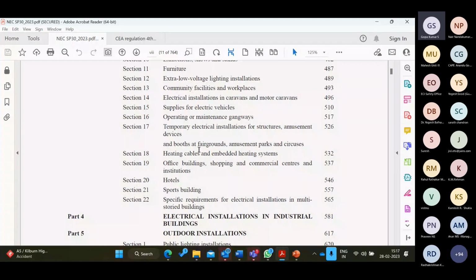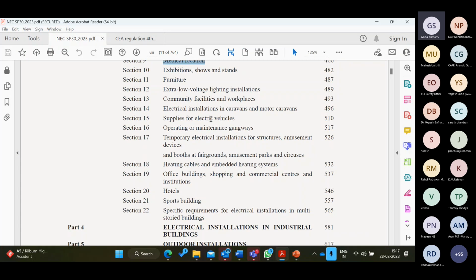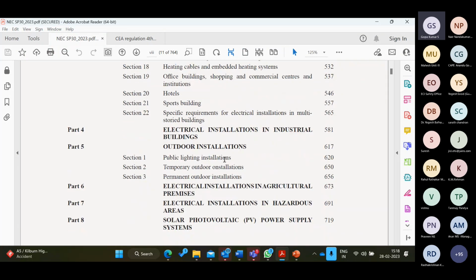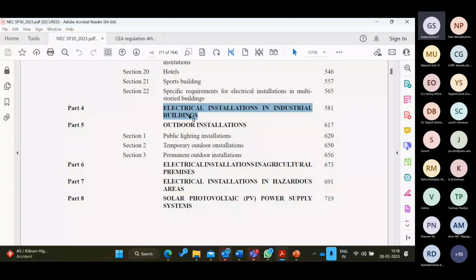This part consists of, again, 22 sections. These special installations are, for example, hotels, industrial, the electrical installation in furniture, operating and maintenance gangways, something like that. Part 4 talks about electrical installation in industrial buildings. This is exclusively for industrial buildings. Then part 5 talks about public lighting installations, temporary outdoor installations and permanent outdoor installations. Part 6 talks about electrical installation in agriculture. Part 7 is hazardous area, part 8 is solar PV. So these are the contents of the National Electrical Code.